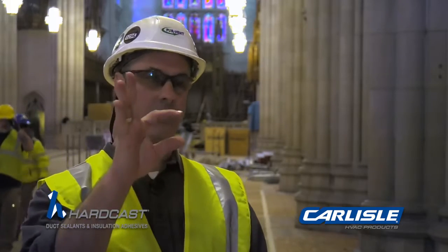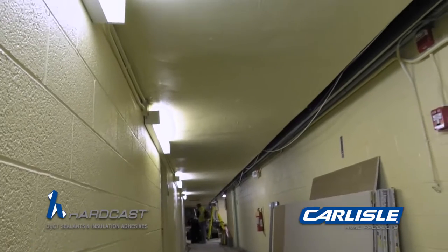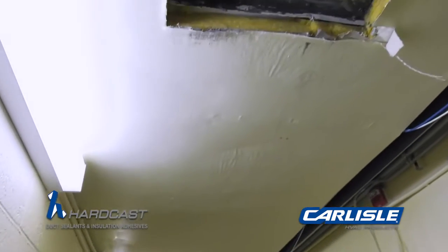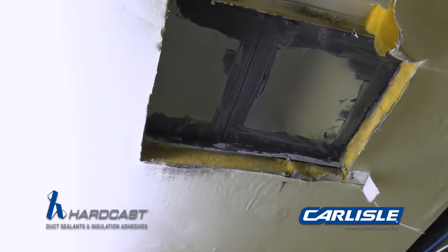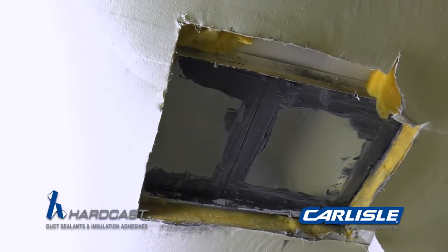Architects and engineers are starting to realize that you can't just replace an air handling unit and leave the ductwork and air distribution at 30 years old with dirt caked on that thick. It just doesn't work, especially if you put new ducts downstream from it. I've seen dirt from old ductwork blow into that, and then they had to clean the whole thing.